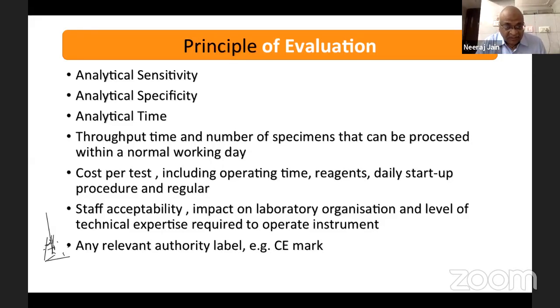Analytical time: how much time it will take in one cycle to measure something, and also see throughput time. Suppose you are able to check 20 samples in 20 minutes, but after that some washing cycle is required, or you have to stop the machine for 30 or 40 minutes because of excess heat generated during that analysis, so your throughput will reduce. You see how many samples you can process in a normal working day. Cost per test, including operating time, reagents, and daily startup procedure. All these things add to your cost per test. It is not only the reagent cost. Staff acceptability: how much technical expertise is required.